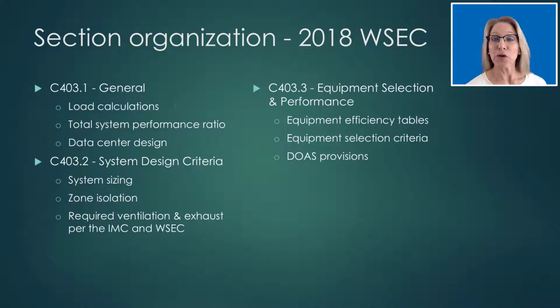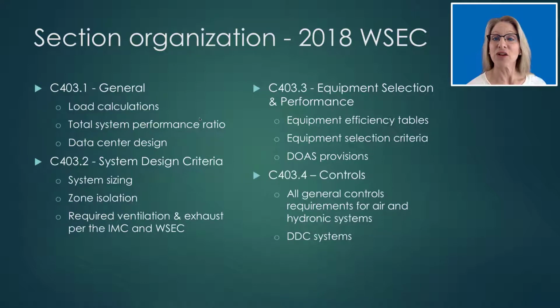In section C403.3, this includes all the equipment efficiency tables and specific equipment selection criteria, such as the requirement that packaged electric heating and cooling systems above a certain size must be a heat pump. This is also where all of the DOAS provisions are located. All of the general control requirements are grouped in section C403.4. So this is where you'll find thermostatic and off-hour control requirements, general hydronic control requirements such as pump isolation and variable flow criteria, and the DDC requirements.